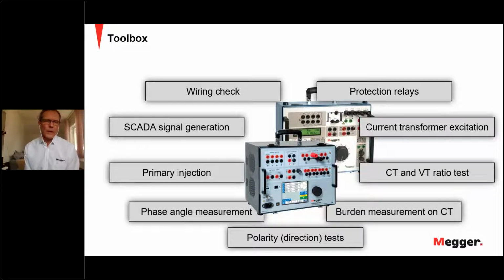You can do wiring checks, you can check SCADA, signal generation, primary injection, phase angle measurements, polarity direction tests on the CTs and VTs, burden measurement test on CTs, CT and VT ratio test, and also current transformer excitation testing. But of course, you can use it to test protection relays. So it's covering a lot, and that's very important.